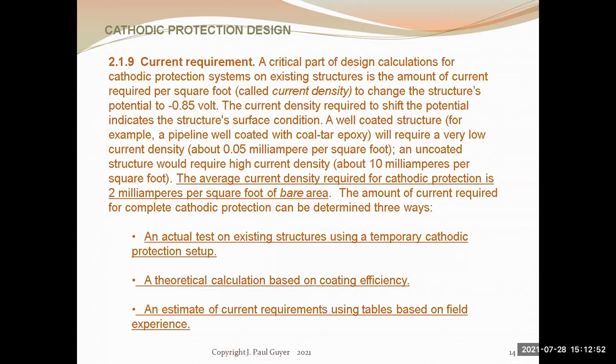Now, an important point to emphasize here in calculating using the 2 milliamperes per square foot rule of thumb is we're talking about bare area of the protected structure. And I said at the start that you've got two tools to use in protecting the structure, coatings and cathodic protection.